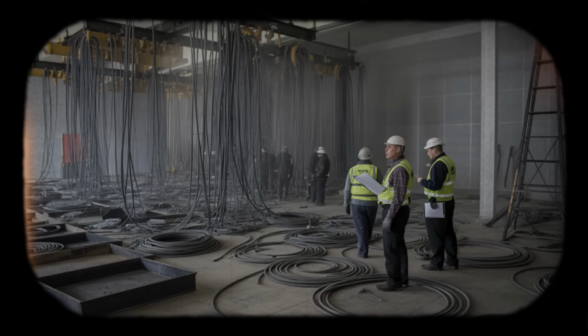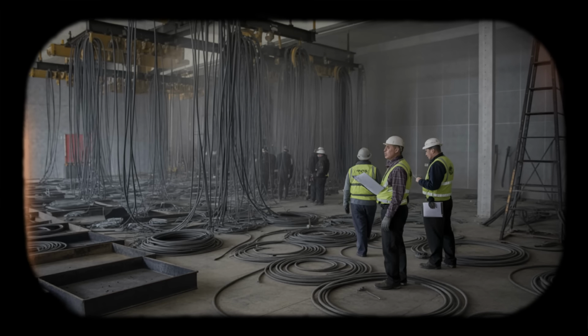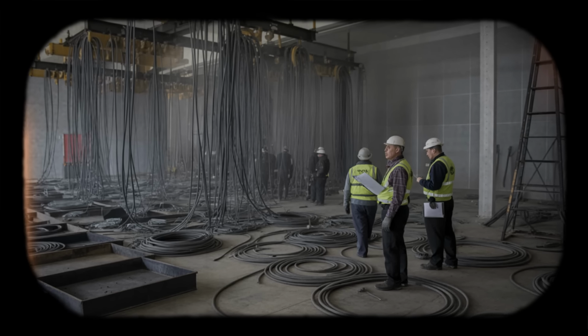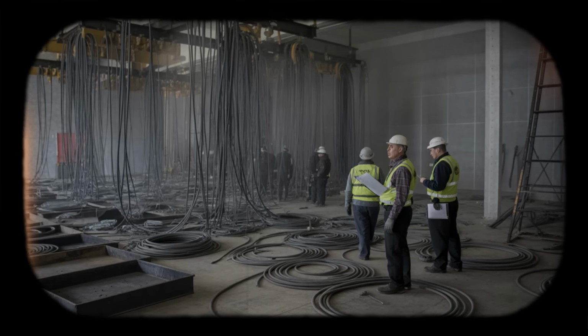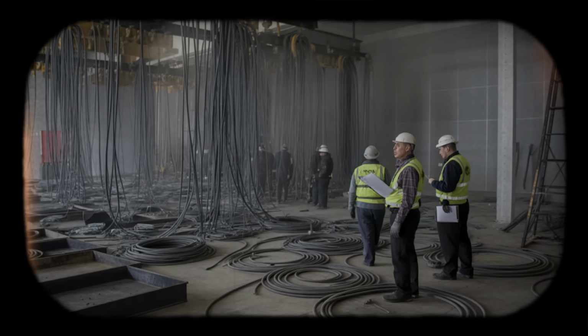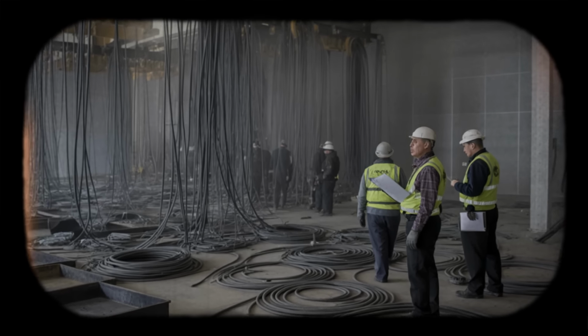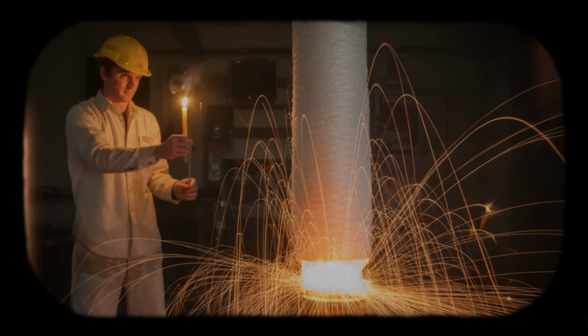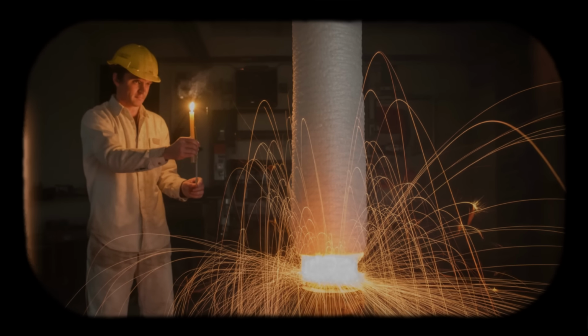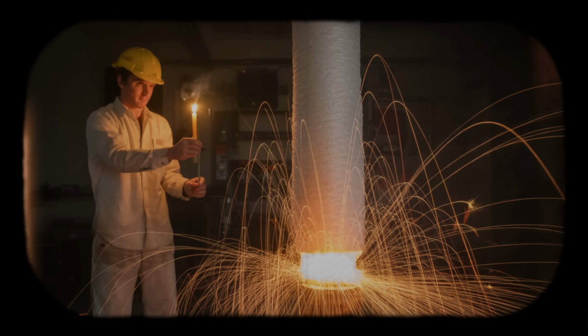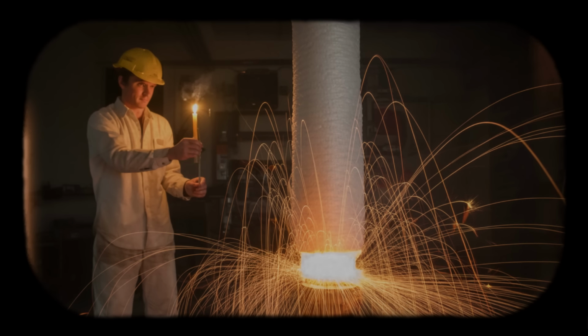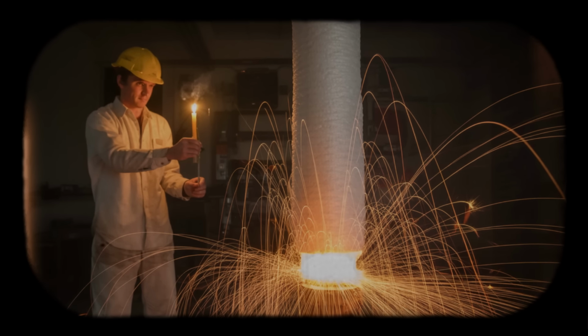Penetration seals were installed where cables passed through concrete walls. Their purpose was to limit air leakage between rooms, not to prevent fire spread. The seals consisted of polyurethane foam applied around cable bundles. As they entered metal sleeves embedded in the wall, the foam expanded to fill gaps. It was considered adequate for air sealing. No one had tested how it would behave under fire conditions. No regulation at the time required fire-rated barriers for cable penetrations in nuclear plants.